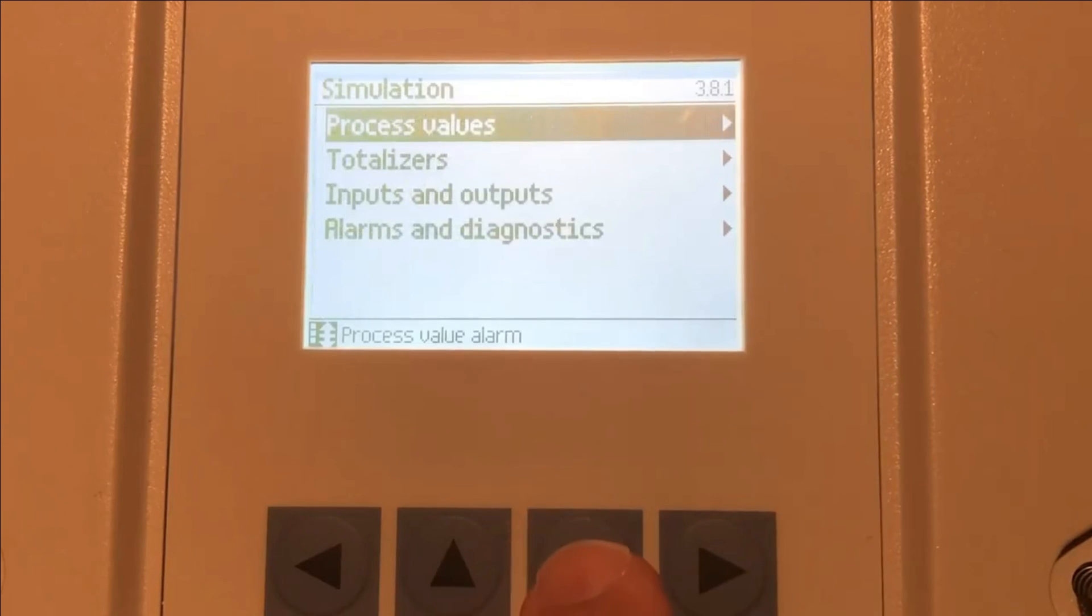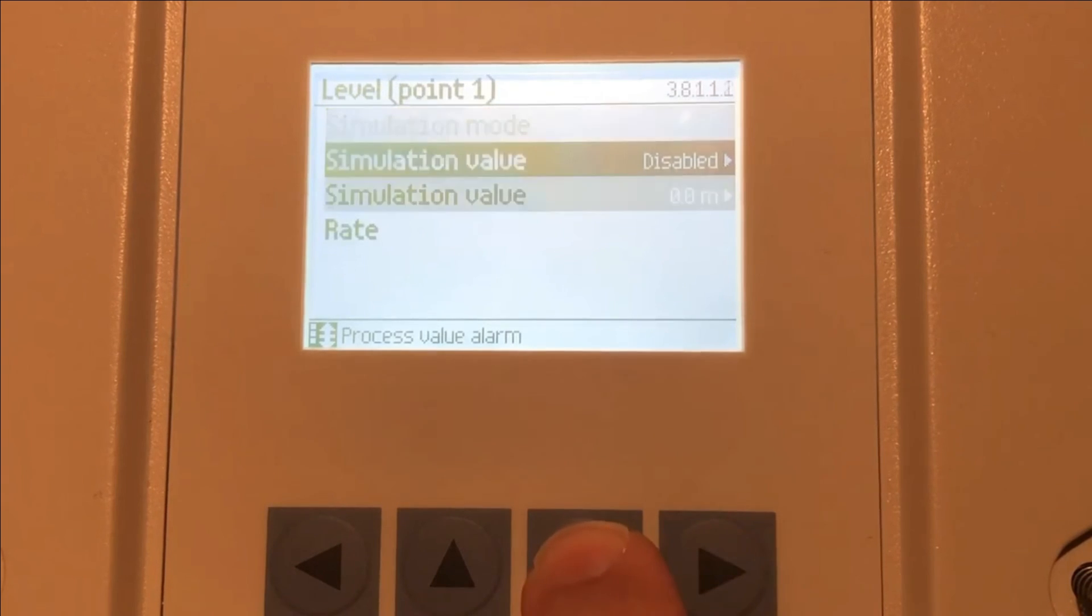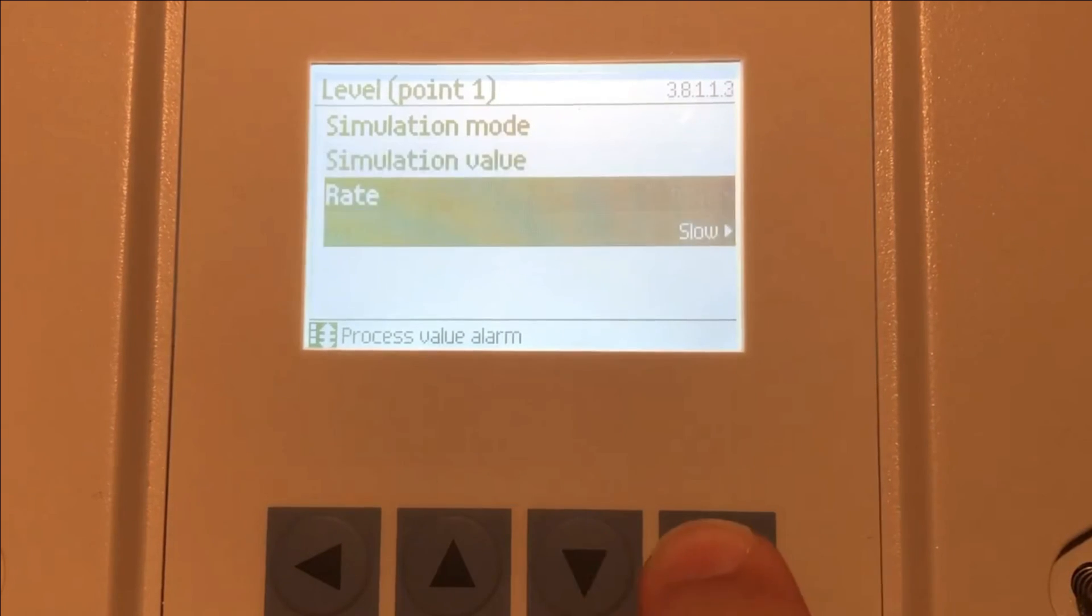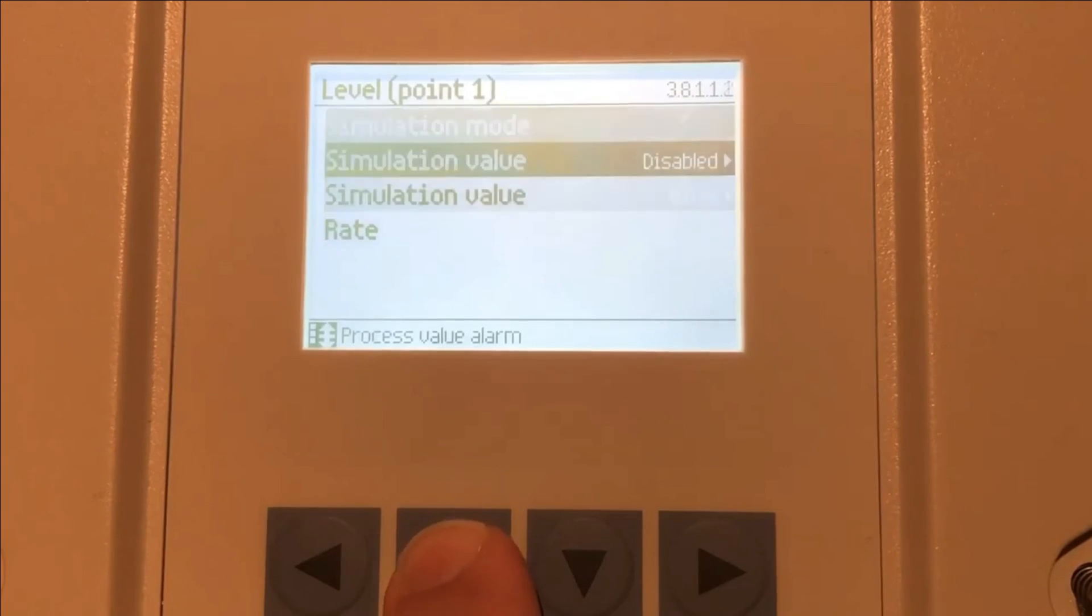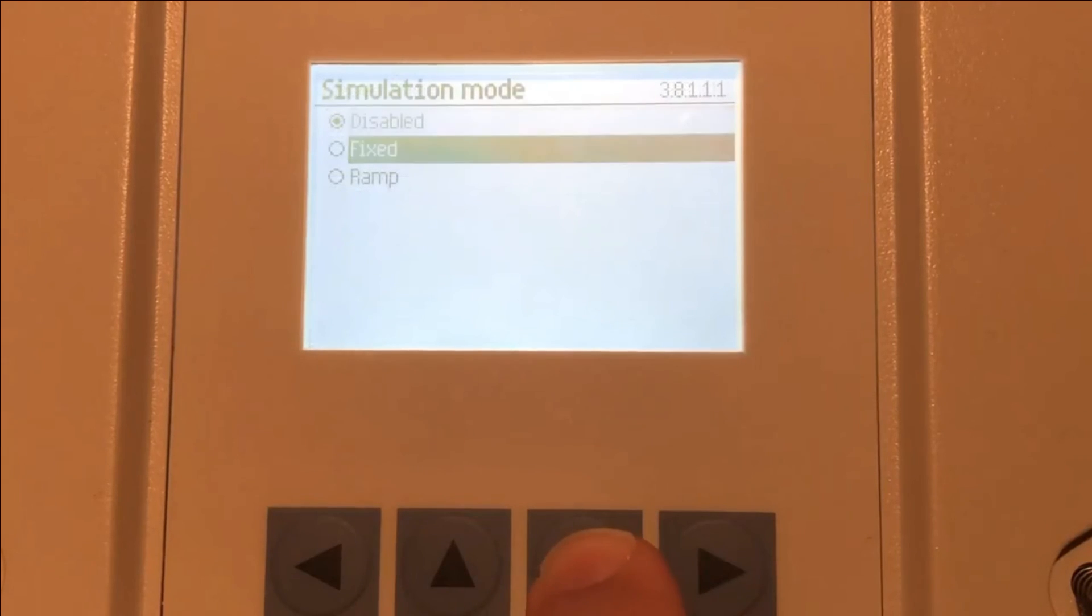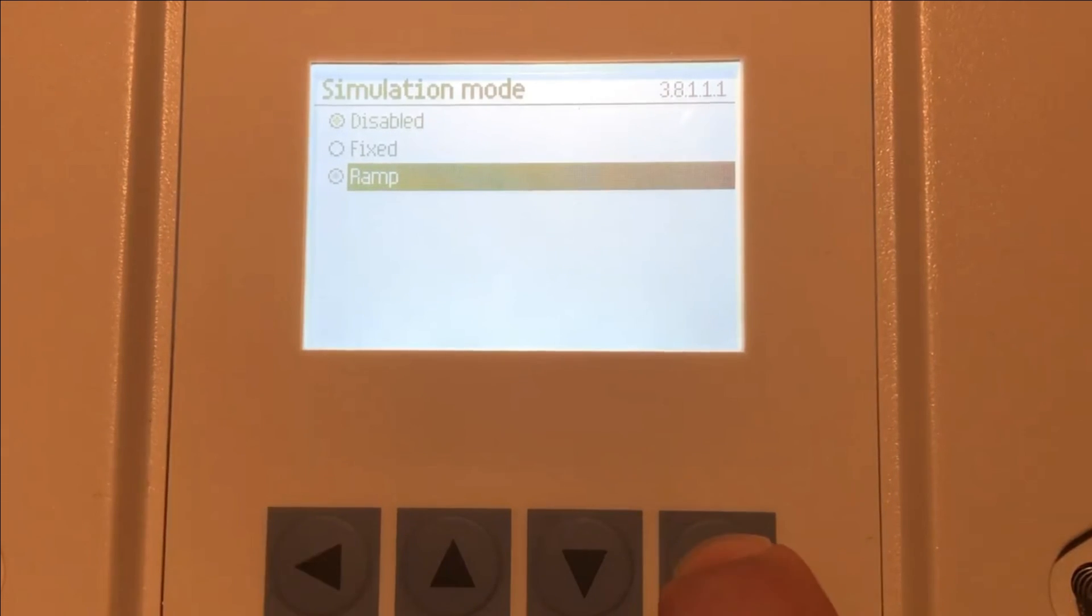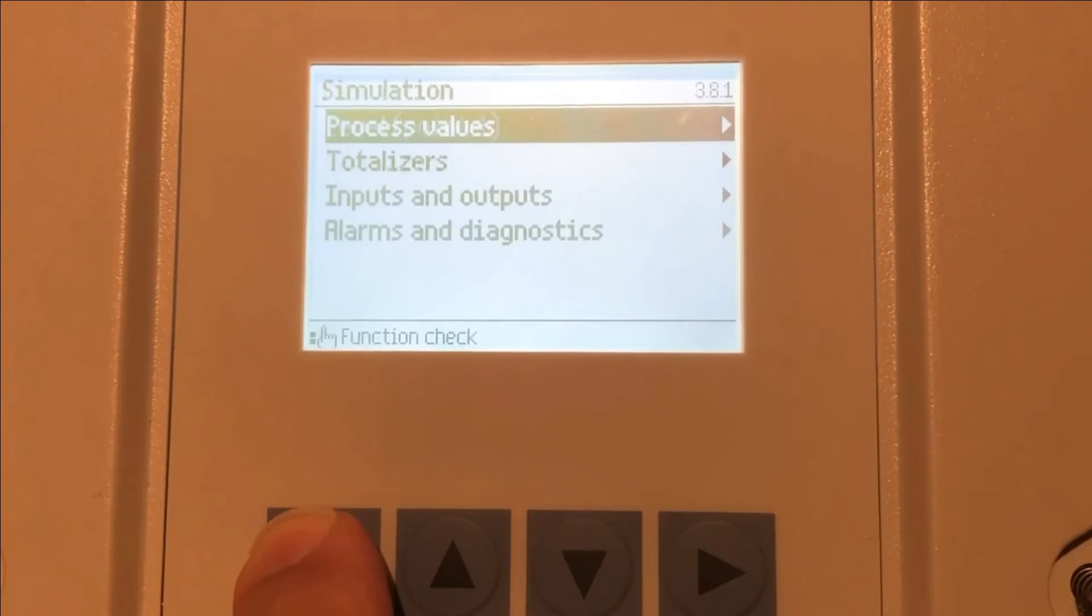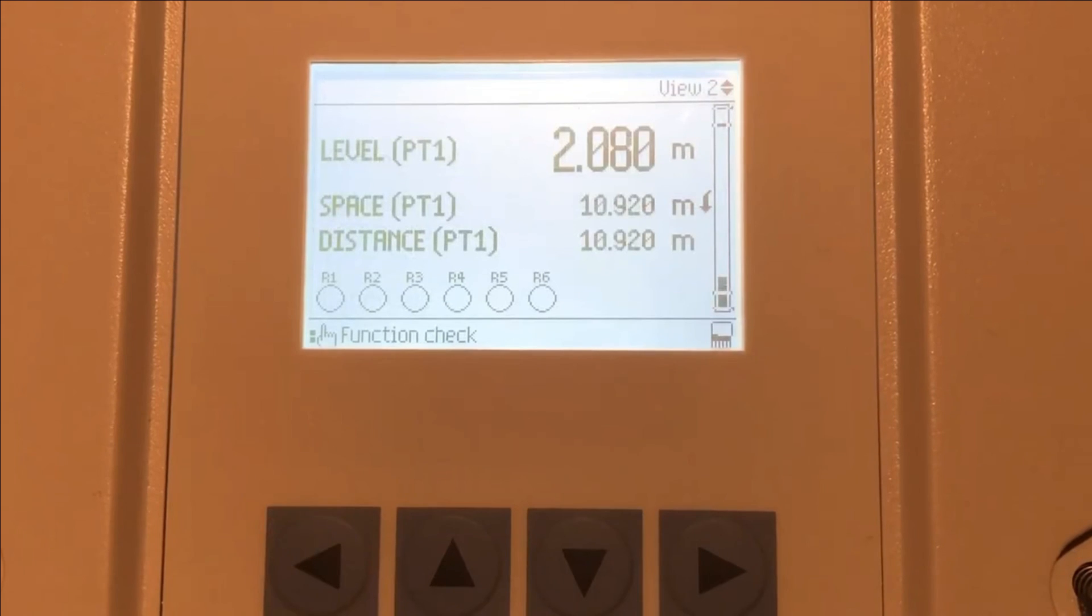So if we go into the simulation menu and under process values, we're going to simulate level, point 1. Our simulation will start at zero meters and it will run fast so that we can see changes quickly. And we're going to use a ramp simulation so that our process value will go up and down over its entire set point rather than a fixed value.